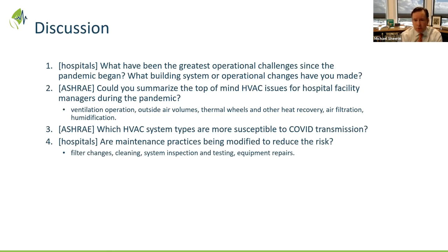That I would challenge your team, if you want to make your facility even better—and I know you've all spent an exhaustive amount of time in the work you've done to date—look at those few areas where there is staff to incoming patient or new patient interactions. You've no doubt built Lexan barriers for those. Look at where the supply grill is versus where the return or exhaust grill is in that space, and if it's not from the scenario you'd know to be safest to the less clean, then think about where those items may need to be changed.